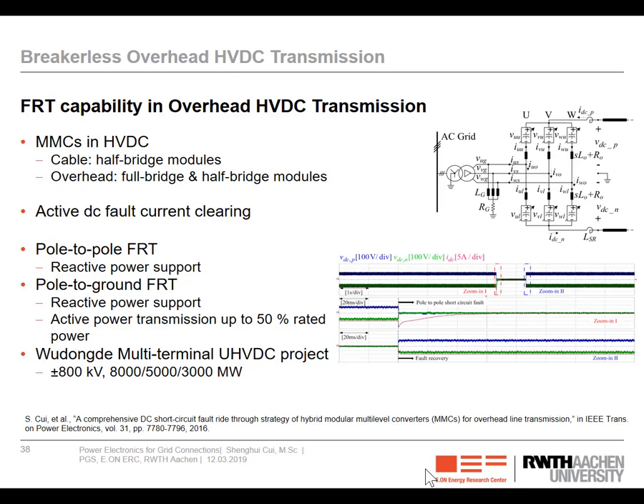And as you can see here, as soon as the short circuit occurs, the DC link current immediately increases. And as soon as the fault is detected, the converter immediately transits into fault ride-through mode. So the DC link voltages, these are the two pole-to-ground DC link voltages, immediately go to zero, and then the fault current is naturally extinguished over a certain time. And then when the current is nullified, the fault is isolated so that we can restart the grid operation.